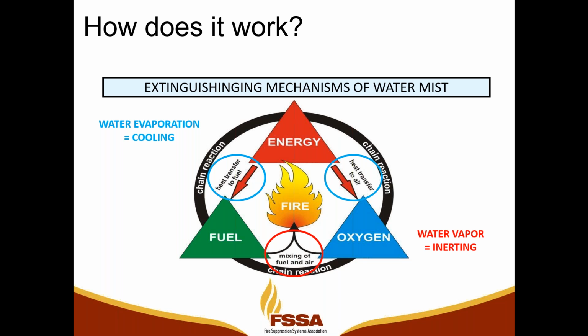Also, when the water vapor is being pulled into the core of the fire, you're creating that local inerting type of environment at the core of the fire, therefore cutting off the fuel and oxygen sources. You're also doing some wetting of the surrounding area, just as with a traditional sprinkler system, just not as much. And basically, this wetting will prevent other fuels from becoming involved in the fire itself.